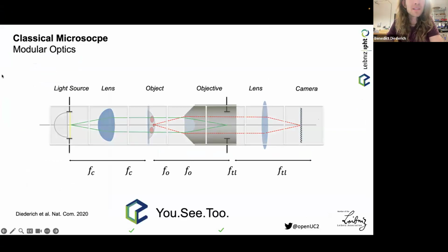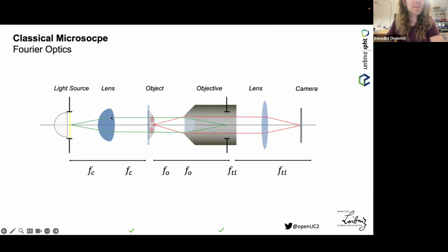Right, so from the microscope point of view, you have an illumination. The illumination is being collimated. This typical thing is called Köhler illumination. You then illuminate your sample with nicely shaped light, because it's all parallel, and homogeneous in the best case. Then you have your microscope objective lens, and a second lens, usually called the tube lens, forms an image on the camera. This is usually called Fourier optics, infinity corrected optics, or 4F or 6F systems. What's important is that these different focal lengths snap into one another, so that the focal length of this lens follows the one of that one, and so on.